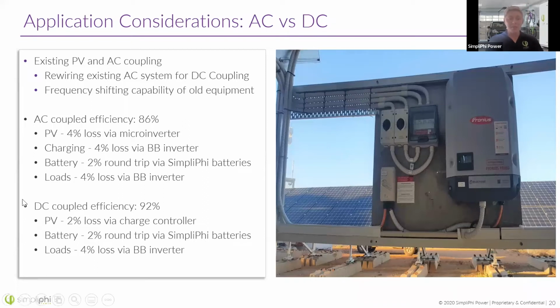Whereas a DC coupled system, it's going from the PV to the charge controller, smaller loss, through the batteries, and then out through the battery-based inverter. It's a much quicker trip there and a more efficient trip. This assumes, though, that you're always charging the batteries before powering the loads. The argument I often hear is, well, I'm going to go with an AC coupled system because I'm sending all the power to the loads immediately. This is really not the case.